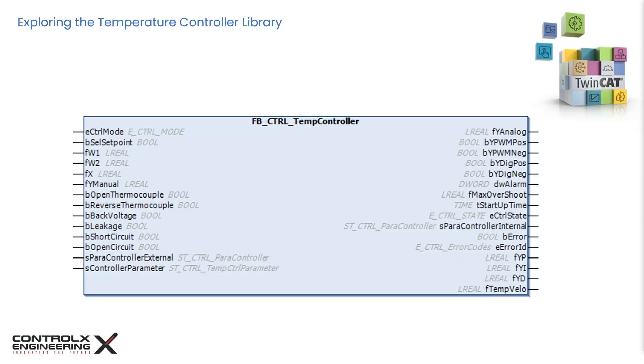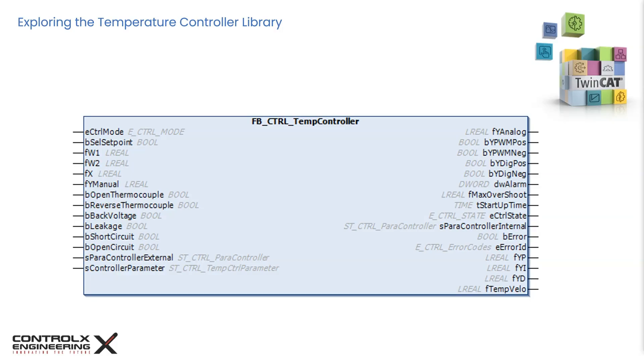Similarly, the setpoint can also be limited to permitted minimum and maximum values which can also be ramped. A bit is available in the interface to the function block that provides easy switching from the actual setpoint to a standby setpoint. A soft start can be parameterized to support heater baking. This involves the setpoint which can also be ramped, being initially set to a low value, remaining there for a certain period of time and then changed to the true setpoint which can again be ramped. The actual value can be digitally filtered. The control algorithm is PID based and additional pre-controller can also be inserted in order to minimize overshoot.